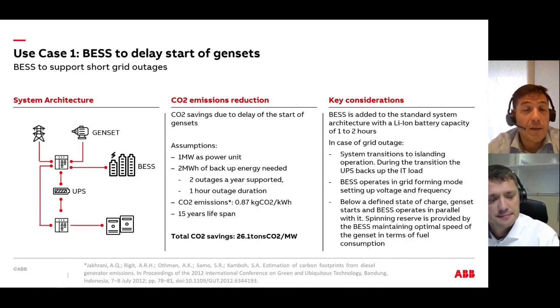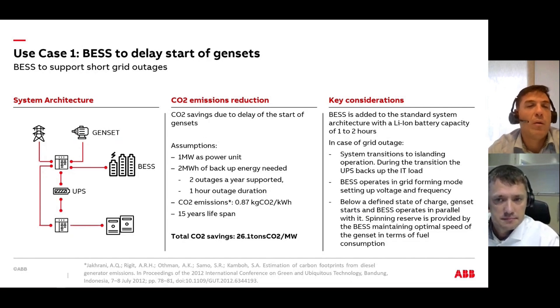So the energy storage can pick up a load within 20 milliseconds at full load, but we have to consider that we have breakers upstream. So we have to consider the opening time of those breakers so that we don't feed a possible fault upstream in the system. If we have to say a number, we would like to stay below half a second. Very good.